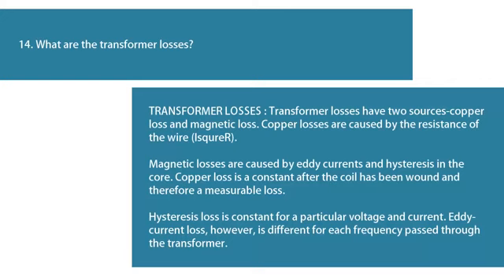Question 14: What are the transformer losses? Transformer losses have two sources: copper loss and magnetic loss. Copper losses are caused by the resistance of the wire (I²R). Magnetic losses are caused by eddy currents and hysteresis in the core. Copper loss is constant after the coil has been wound and is therefore a measurable loss. Hysteresis loss is constant for a particular voltage and current. Eddy current loss, however, is different for each frequency passed through the transformer.